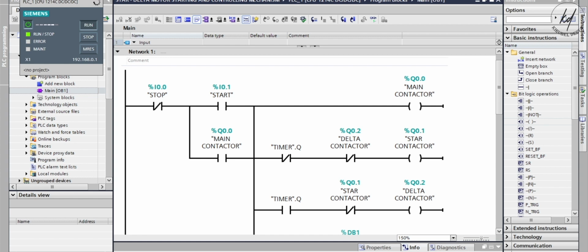This starting method only works when the application is light loaded during the start. If the motor is too heavily loaded, there will not be enough torque to accelerate the motor up to speed before switching over to the delta position. When starting up pumps and fans, for example, the load torque is low at the beginning of the start and increases with the square of the speed.